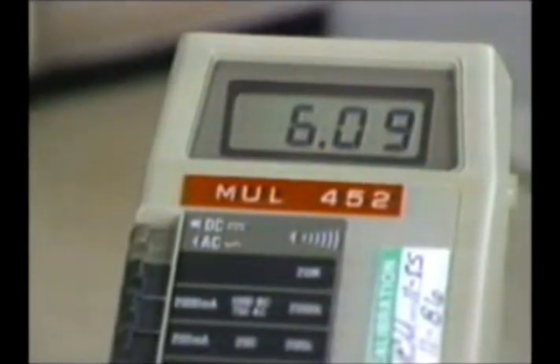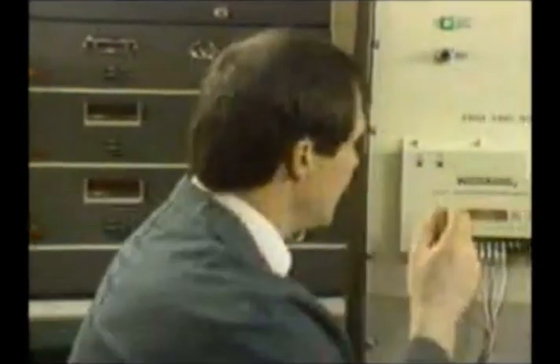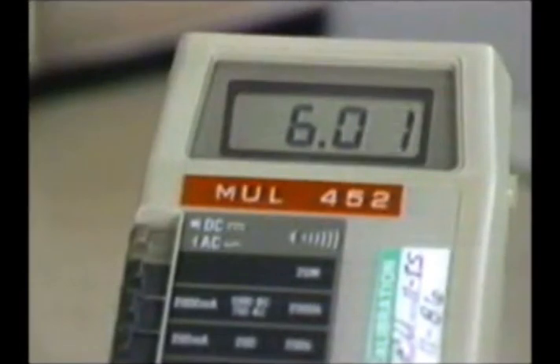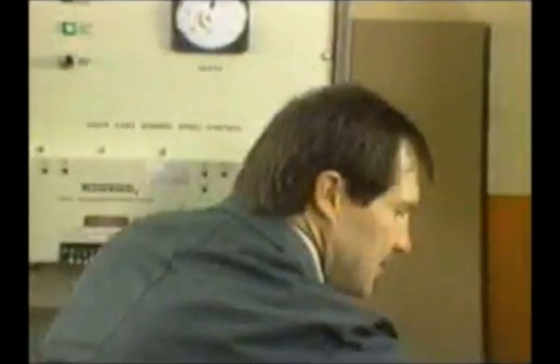We're reading a little bit high, and that's because these resistive load banks aren't exactly equal. So when I said I was at a third load, I was a little bit underneath that. But this should get you very close for your load sharing lines. So now let me go ahead and tweak that down so it reads 6. So now we're reading right around 6 volts on the load gain. Now if I take all my load off, that load gain voltage will come back down to 0.